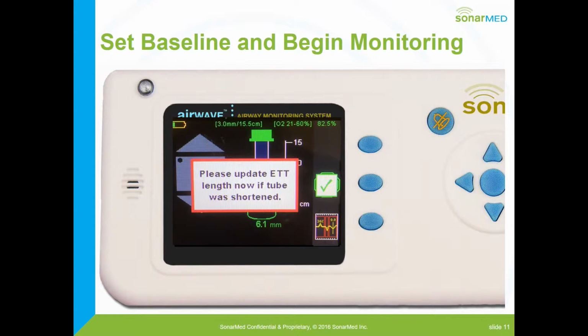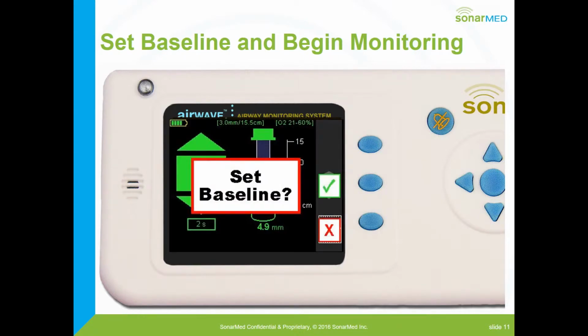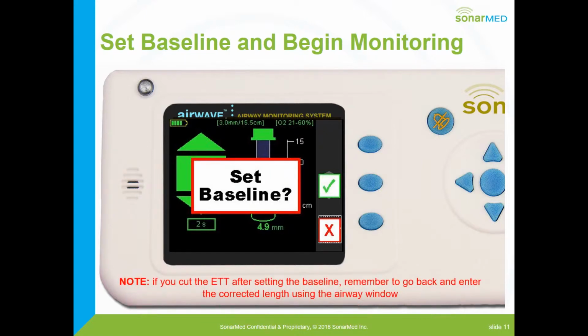And then I want to set baseline by pushing the button and confirming that I've set baseline. You do this at the very beginning, and basically what you're saying is this is where the tip of the endotracheal tube is at this time. If after you set the baseline, you cut the tube, then go back and enter that correct length later on.